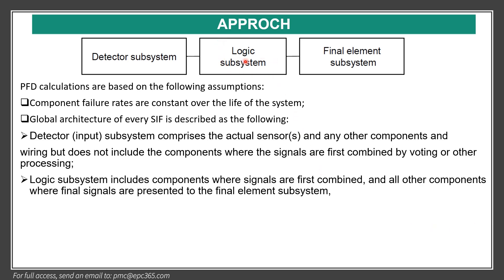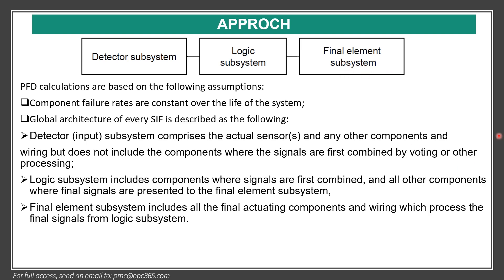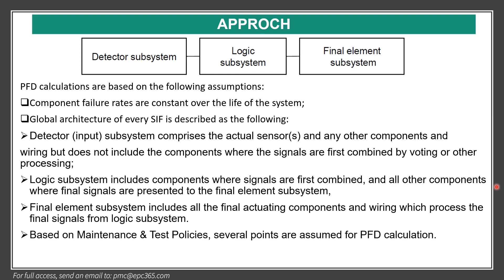The logic subsystem includes components where signals are first combined and other components where final signals are presented to the final element subsystem. The final element subsystem includes all final actuating components and wiring which process the final signal from the logic subsystem. Based on maintenance and test policies, several points are assumed for the PFD calculation.